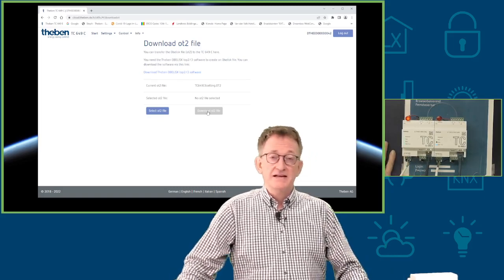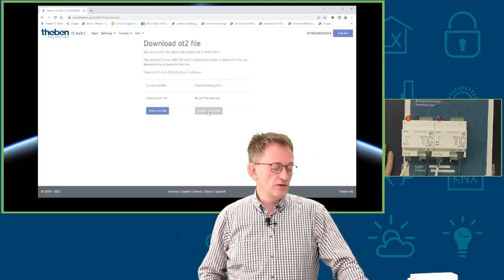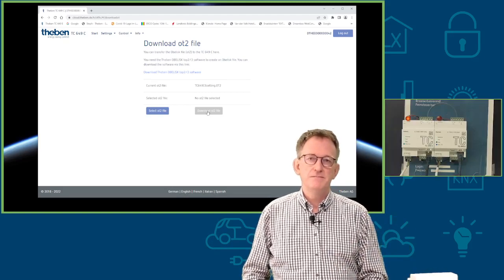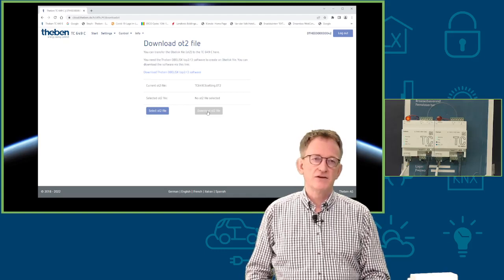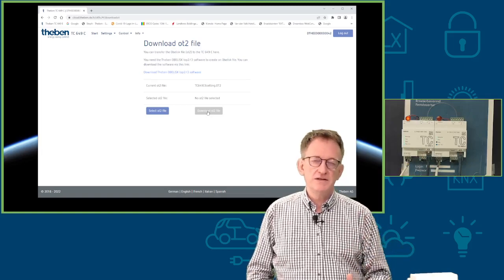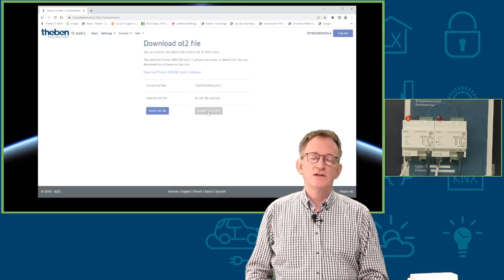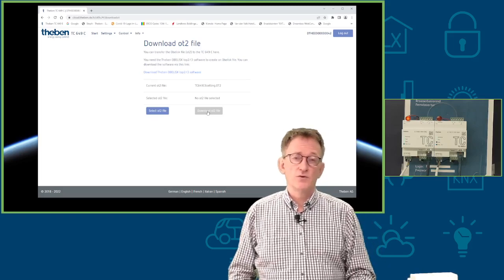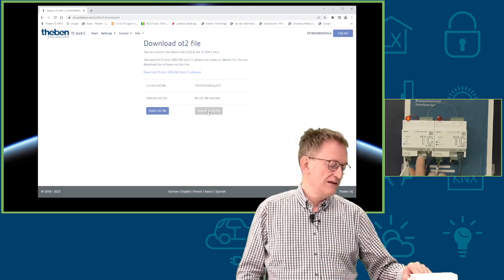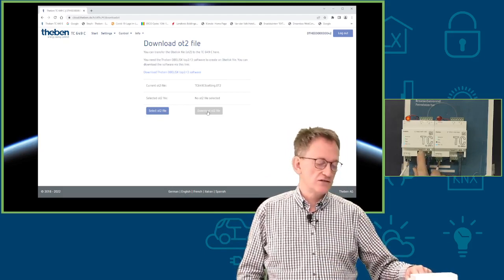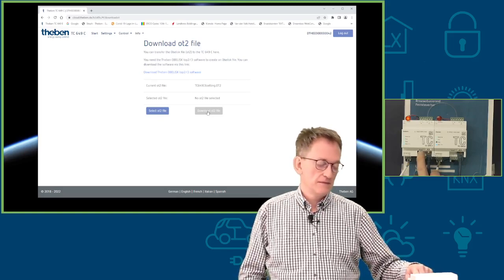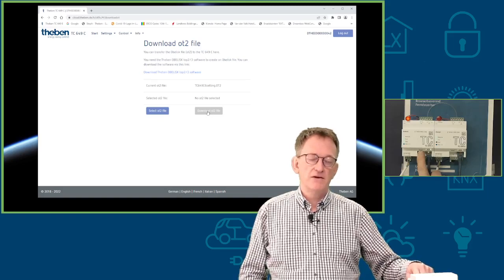For example, if somebody connects a laptop to that network and now suddenly he got an IP address which is completely different and independent of the customer network. And so the PC might get a wrong IP address, cannot communicate in a network, and the client will complain, my laptop is not working. So that's really the reason. Please be very careful. Never ever connect the service port to an existing network. Very, very important.